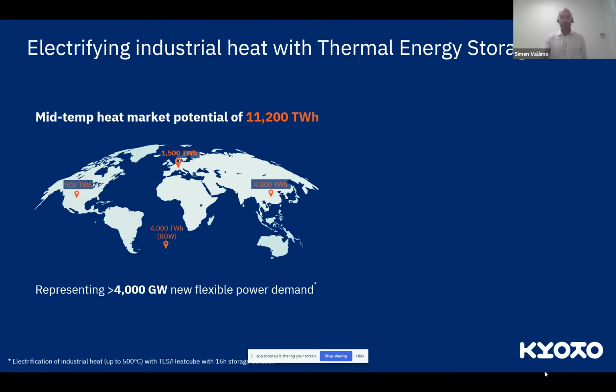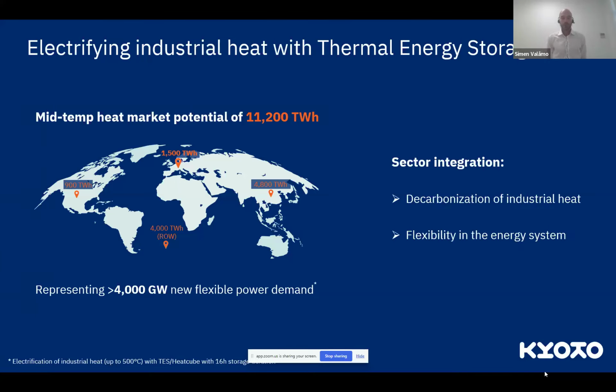This is because a thermal energy storage asset doing power to heat has a longer duration storage. Typically it would be sized so that you charge around 8 hours per day while providing heat 24 hours per day, representing 16 hours of storage duration. So what you're doing here is sector integration: electrifying the industry, decarbonizing one of the biggest contributors to CO2 emissions, while at the same time solving the challenge of flexibility in the energy system.